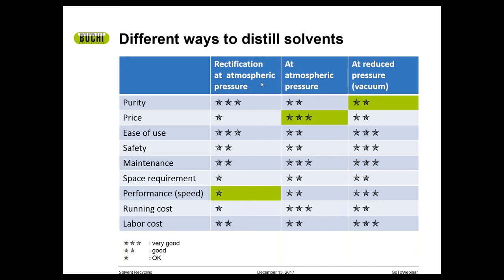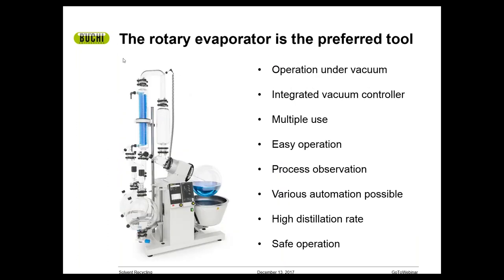The rotary evaporator is the preferred instrument for this process. Here at Buchi we've been doing it for 60-plus years and it's well known within the industry. Using rotary evaporation for concentration is already widely used, so why not use it to purify your solvents as well? Working under vacuum reduces the boiling point like I mentioned, and we have an integrated vacuum controller. The vacuum controller controls the vacuum very precisely, with minimal fluctuation, giving you maximum distillation rates. It doesn't just control the vacuum — it controls everything about the instrument. The rotary evaporator can concentrate, dry samples, and recycle, as we're talking about now.